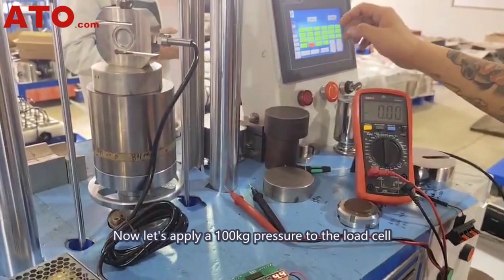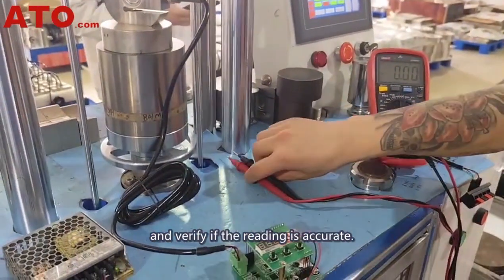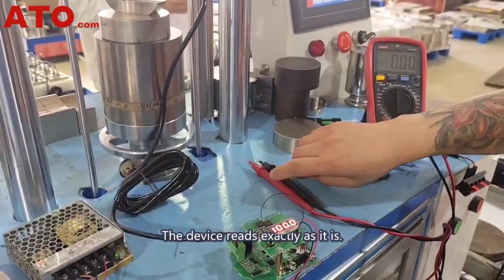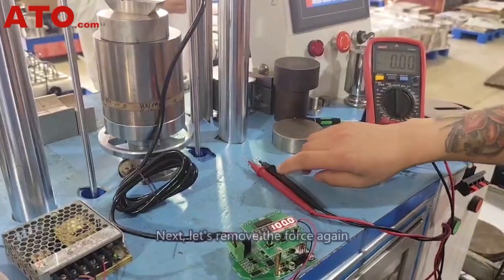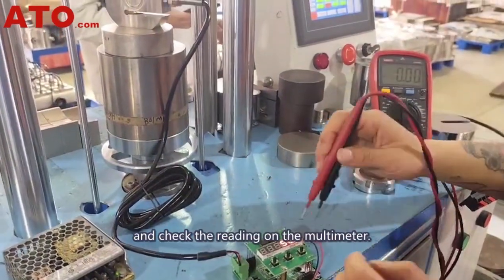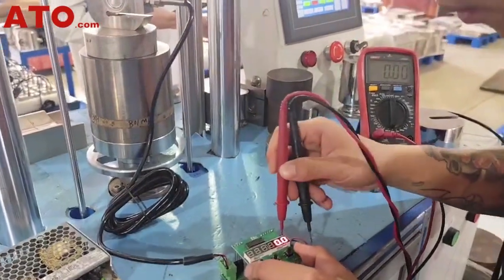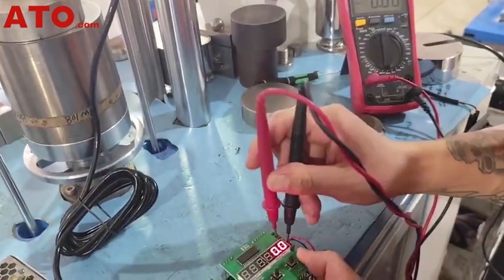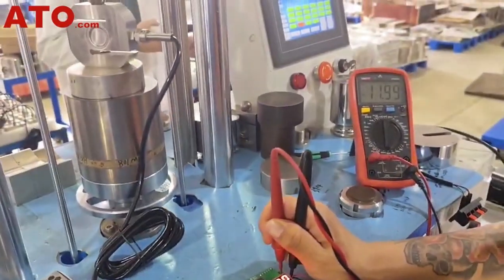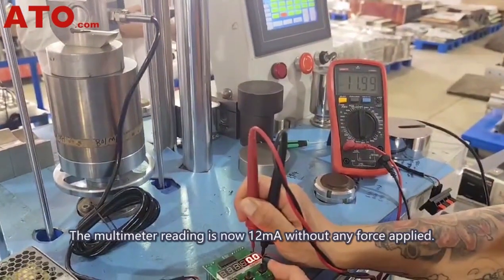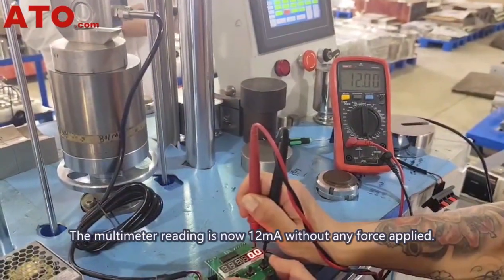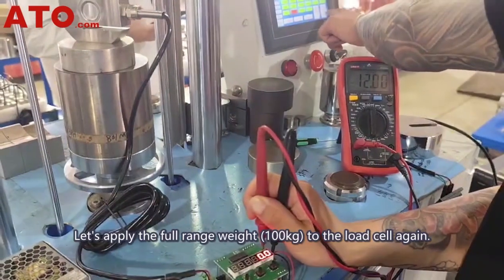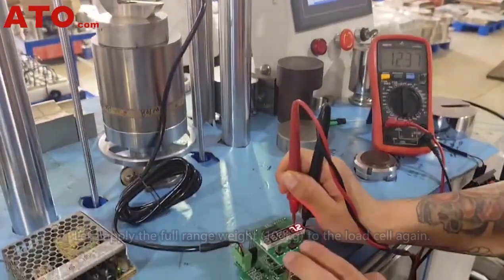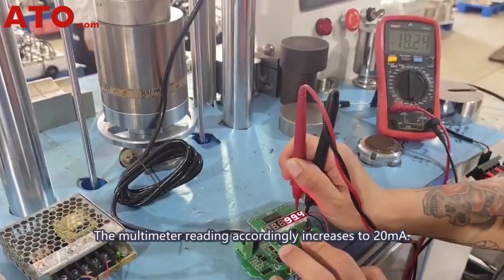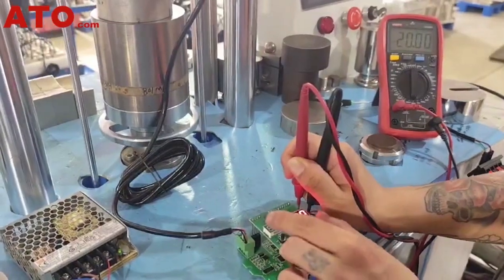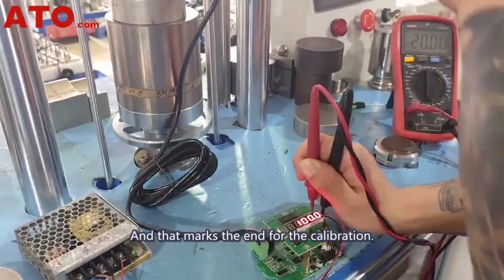Now let's apply a 100 kg pressure to the load cell and verify if the reading is accurate. The device reads exactly as it is. Next, let's remove the force again and check the reading on the multimeter. The multimeter reading is now 12 milliamps without any force applied. Let's apply the full range weight to the load cell again. The multimeter reading accordingly increases to 20 milliamps. And that marks the end for the calibration.